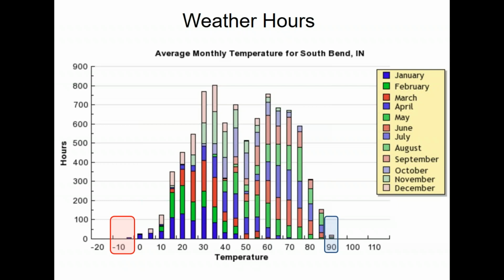So that's why we don't design for those peaks, because it ends up giving us equipment that's 1, 1.5, 2 tons bigger than it needs to be, which means it's really horrific at dehumidification. I'd rather have my cooling be awesome on all of those hours where it's 75, 80, 85 degrees and have it be a teensy bit undersized on the 90-degree day, meaning that the customer can't get their set point down to 74. They can only get it down to 74.2 or whatever number you pick.